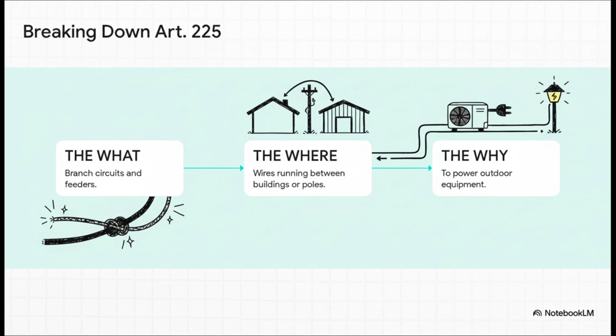The National Electrical Safety Code, the NESC. That's for utility infrastructure. Article 225 is all about managing electricity after it's in the consumer's domain. That is a huge boundary line. Okay, but now we have to talk about the electrical boundary, which is maybe the most important one in the whole article. Article 225 is strictly limited. It's for systems not over 1,000 volts AC or 1,500 volts DC, nominal. That 1,000-volt AC line is the industry's great divide. And we should probably unpack that a little.